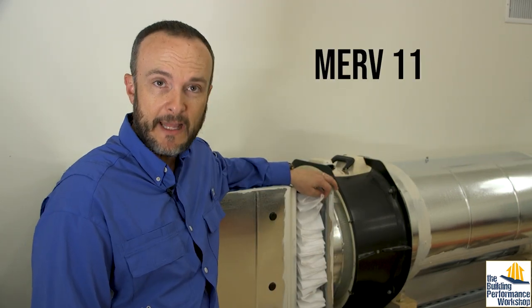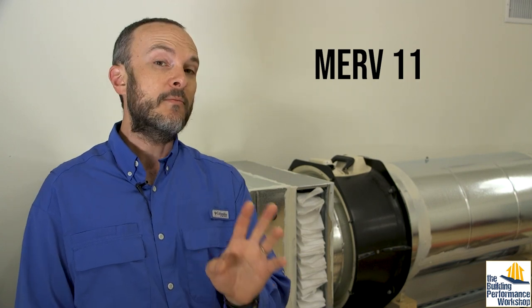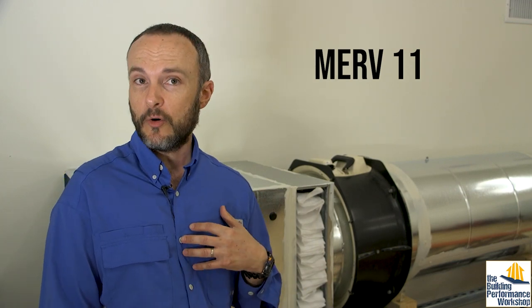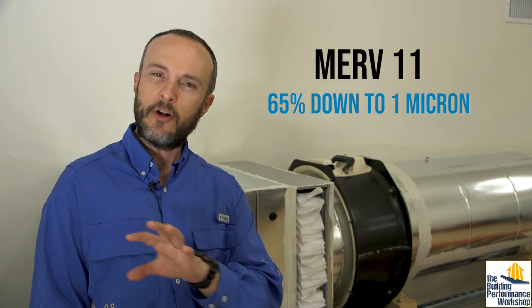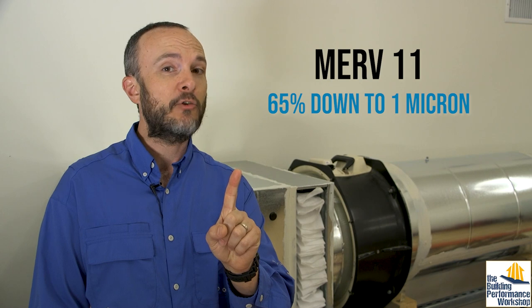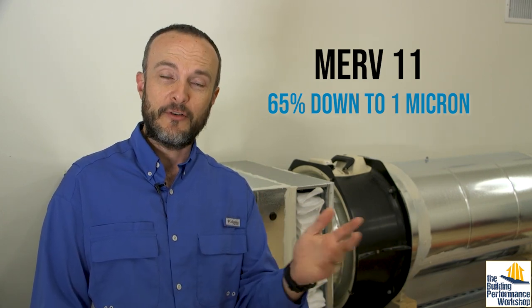This filter is a MERV 11 filter. And MERV 11 is where you start talking about human health. If you're anything less than MERV 11, you're talking about just keeping your house more clean and protecting the equipment that's moving the air. MERV 11 is where you should really invest if you're going to start caring about things that get into your or your kids' lungs. So MERV 11 is going to grab 65% of all of the particles down to about one micron. But it's not going to grab anything smaller than that based on the testing that's from ASHRAE and also from AHRI.